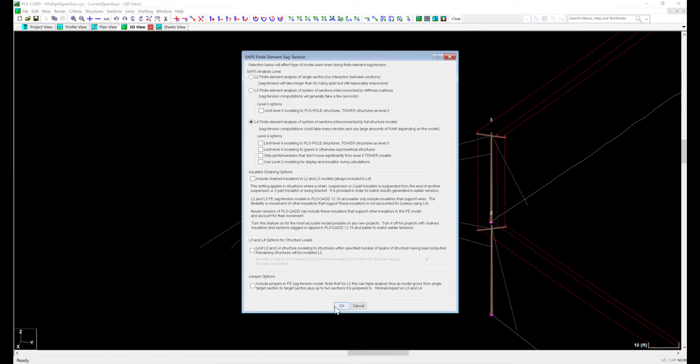In a typical structure check, PLS-CADD opens PLS Pole in the background and performs a structure check. In this example, we are checking two structures and using the interaction with the conductors in PLS-CADD to determine the structural capacity. I'll leave everything else unchecked. Appendix N of the PLS-CADD manual covers L4 analysis and how it works. Powerline Systems also has a video on using FE analysis, which is linked in the description below.